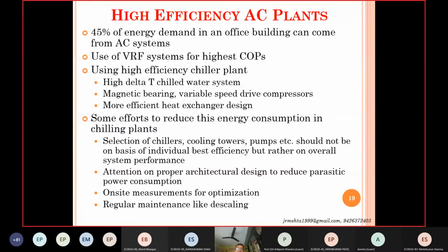So high efficiency AC plants need to be adopted and implemented, because around 45% of the energy demand, let's say in an office building, can come from air conditioning systems. So use of more energy efficient systems like VRF systems. If a chiller plant is used, then high delta T chilled water systems and other technological advances like magnetic bearing, variable speed drive compressors, and more efficient designs of the heat exchanger, the evaporator in particular. Some efforts to reduce this energy consumption in chilling plants are also enlisted here. That's about the optimum selection and combination, and also having an overall view of the system rather than the individual best efficiency of the different parts of the system.